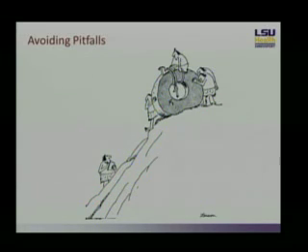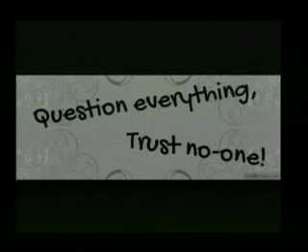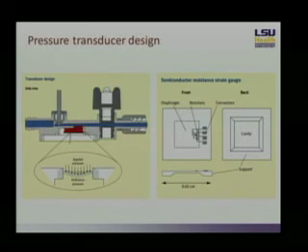The first item I want to bring up — and if you take anything home today, it's this — when you're approaching monitoring in the ICU, you're relying on electronic and fluid systems that, based on a number of assumptions, work well under ideal conditions. It'll be up to you to identify when those conditions may not be present. The first topic is blood pressure measurement. We go see our patients, the nurse hooks it up, and tells us the blood pressure. The goal is for you to decide whether you can believe that number. More often than not, you should not trust that number.